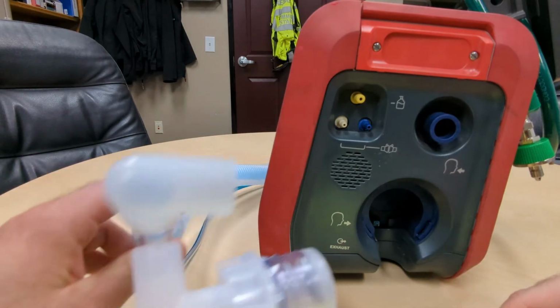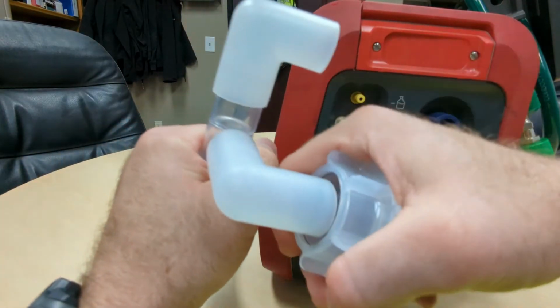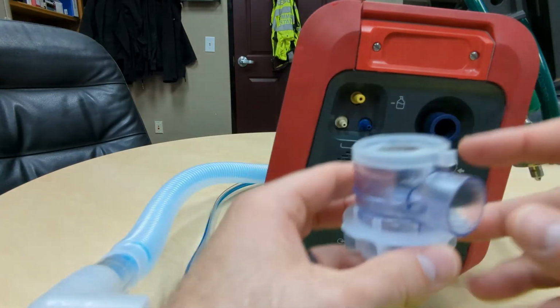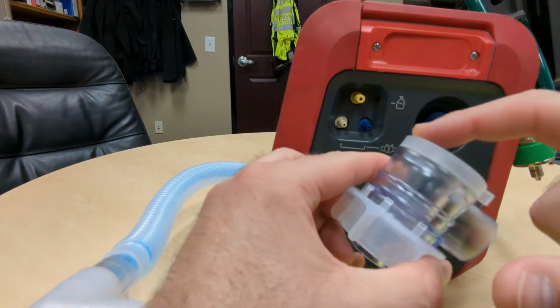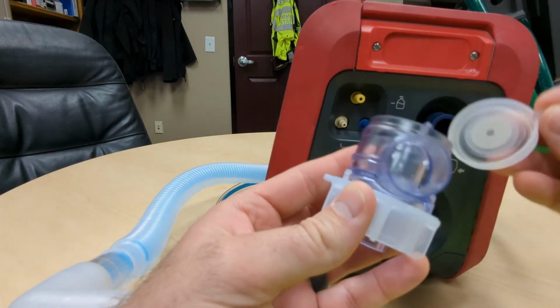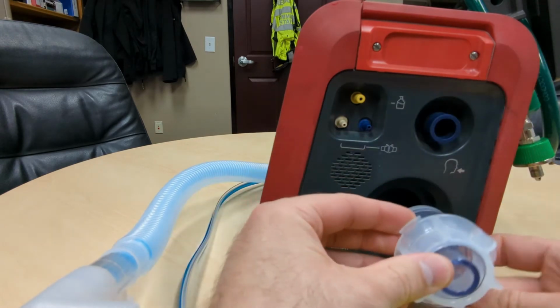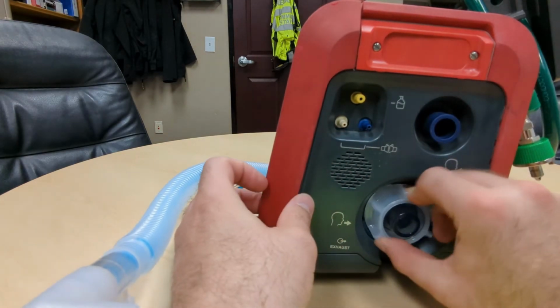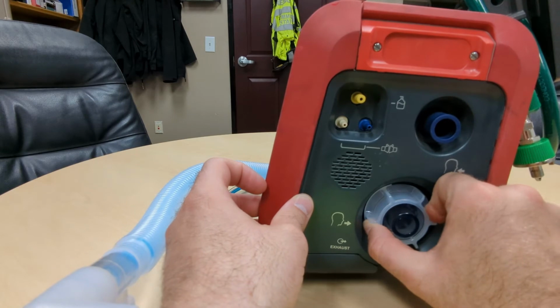So when you get a circuit, it's like this. I recommend taking off the exhalation valve, making sure that this diaphragm is seated on this. So it easily comes off. Make sure that it's seated. It's a quarter turn. So it goes in only one way, and then it turns and locks. You don't need a lot of force to lock it.